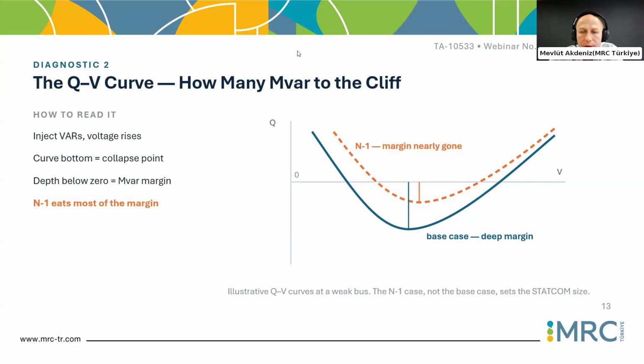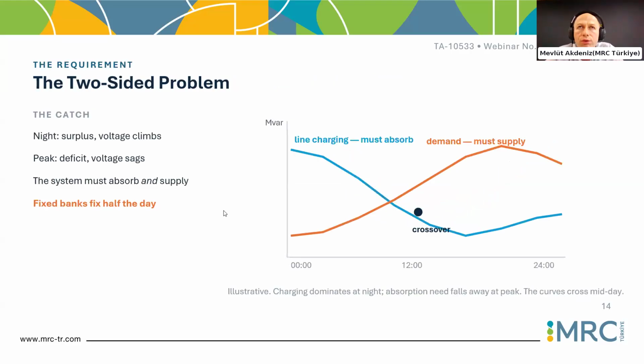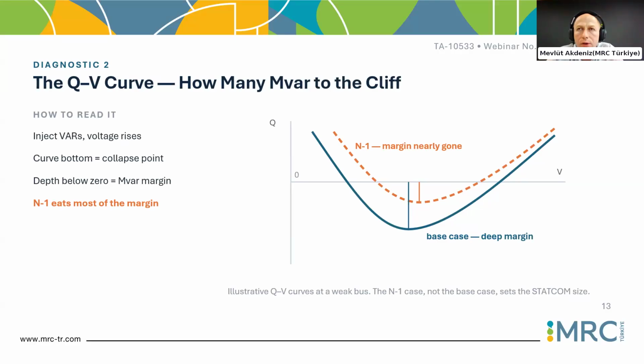We have some operational stable points in the load flow results, and we can also try the n-1 to see the incremental or relative jump, if the bus bar or substation at that region is strong enough or not. So for the point-wise load flow solution, we may converge this load flow solution, so everything goes okay, but the load flow itself does not give some insight regarding these transients based on the reactive power regulation.